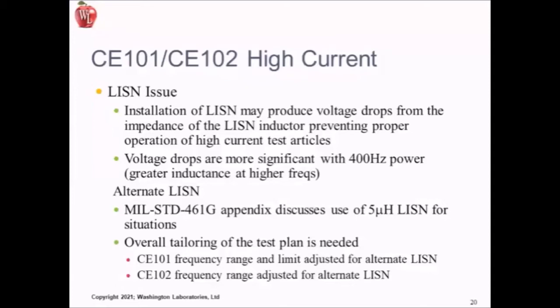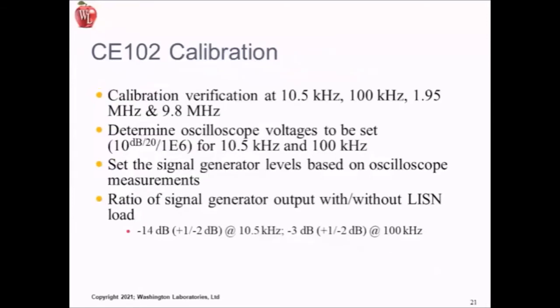Again, the last bullet on the bottom there is consider tailoring. If you have a large current draw type of equipment, you should consider looking at the CE 101 and 102 range adjusted, particularly if you're using an alternate LISN. Again, tailoring. For CE 102, which is a higher frequency measurement, you're looking at basically the range of switch mode power supply type of noise. And so you have to make sure you're doing calibration verification at those frequencies.